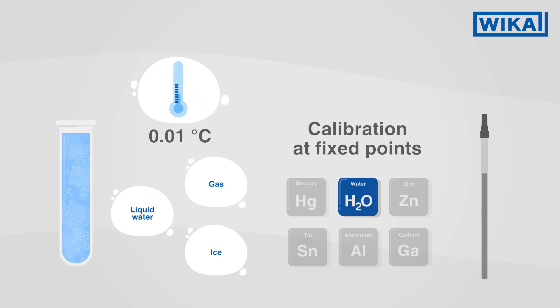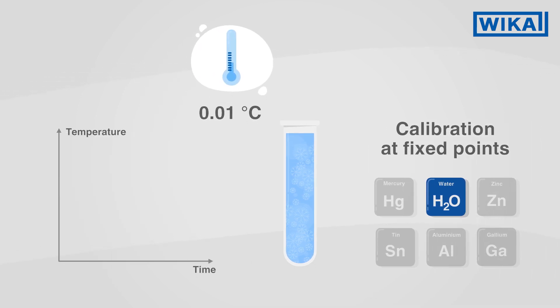The point is defined at exactly 0.01 degrees Celsius. In order to reach the triple point, a time-consuming and complex procedure is needed. Once reached, the temperature remains stable at the triple point for a long time.